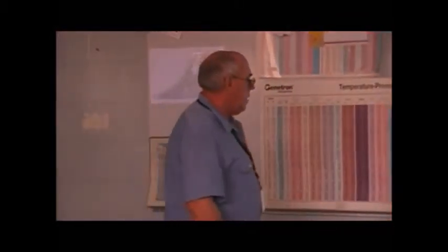Those are appliance loads. Those are internal heat loads. In our case, we're going to use the 1200 just to say that. Now, when you go to the room by room, you must either put all that load in one place or spread it out a little bit in each room, but it must add up to the 1200 BTUs, or whatever your choice is. And here, I'm going to go ahead on the block load and put in my 1200 BTU internal heat gain. All right.